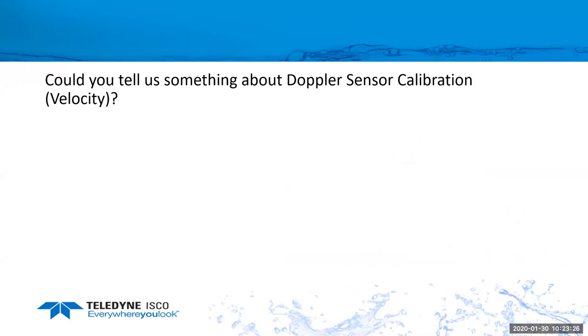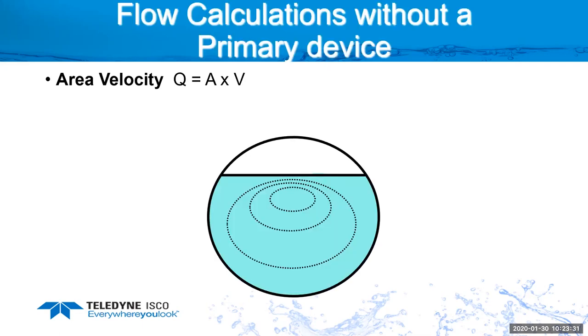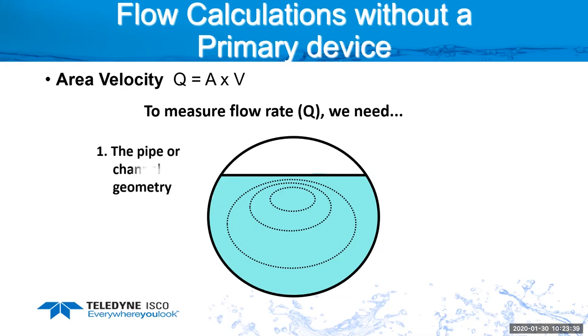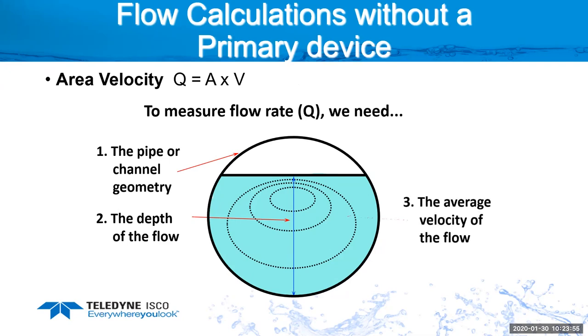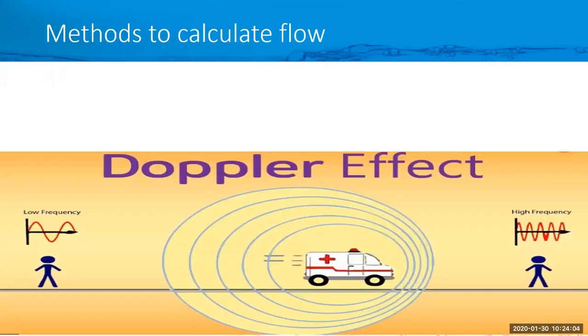Another question was, could you tell us something about Doppler sensor calibration? First, when using an area velocity sensor, the formula is area times velocity to get our flow. So what do we need? We need to know the pipe geometry, whether it's a round pipe, rectangular, or elliptical. We need to measure the water depth. When we know the water depth, we can calculate the wetted cross-sectional area in that pipe. Next, we need the average velocity. With the average velocity and the wetted area, we can now calculate the flow rate.